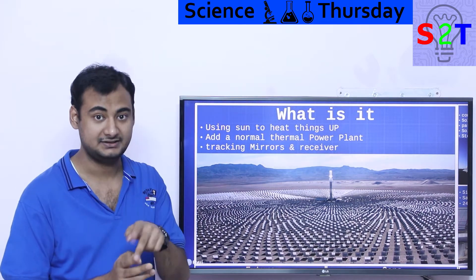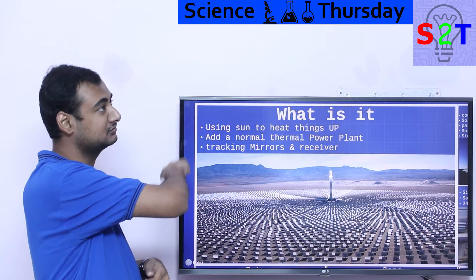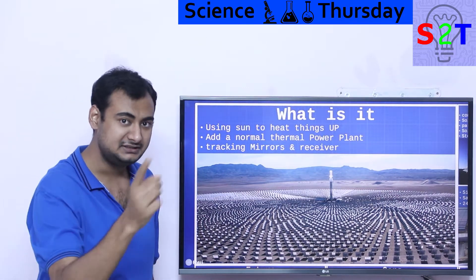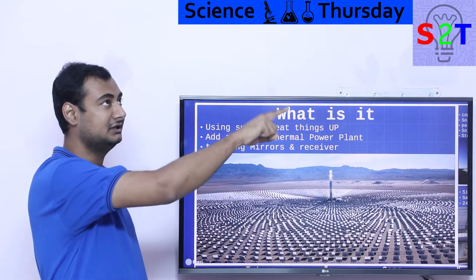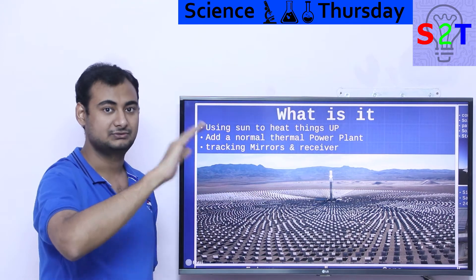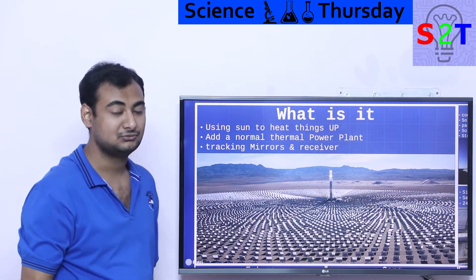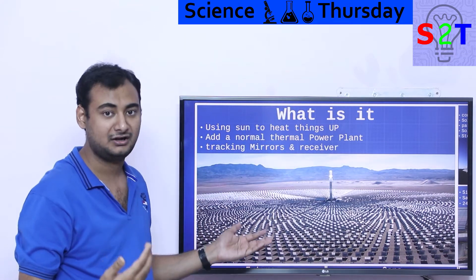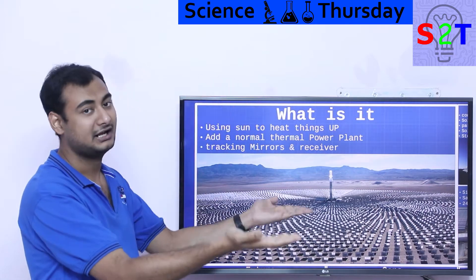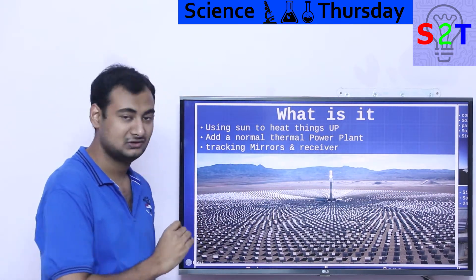The sun moves in two axes. You can try single-axis tracking since the sun goes from one side to the other on a day-to-day basis. But seasonally, the sun's direction shifts — in winter it's lower, in summer it's nearly overhead. So there's a second axis to track as well. If you really want to run a power plant and extract every bit of light, you want to track on a seasonal basis too. That's why tracking is very important for solar thermal systems.